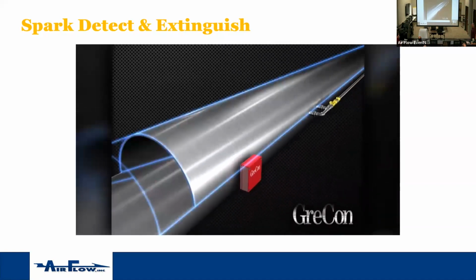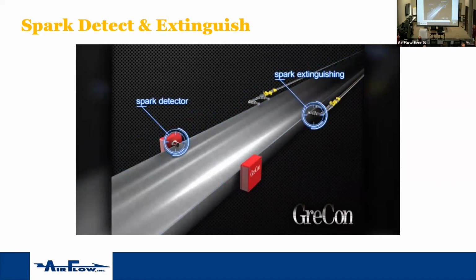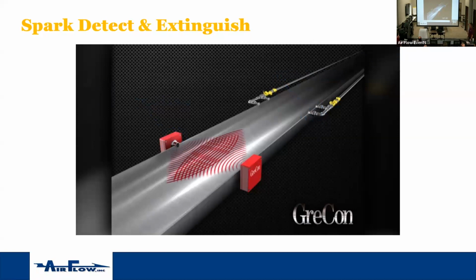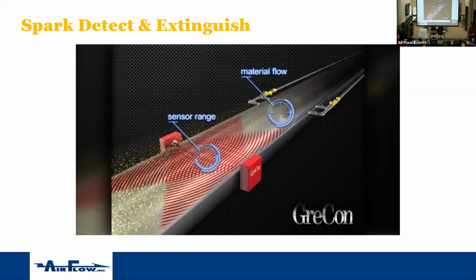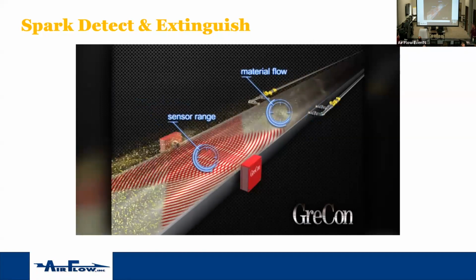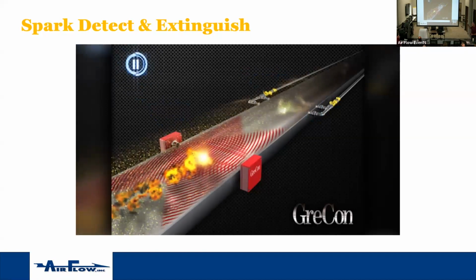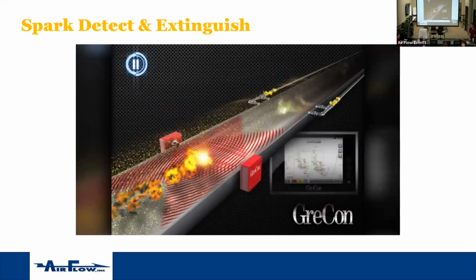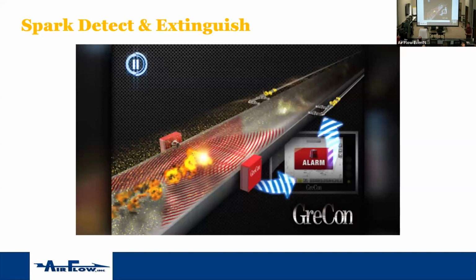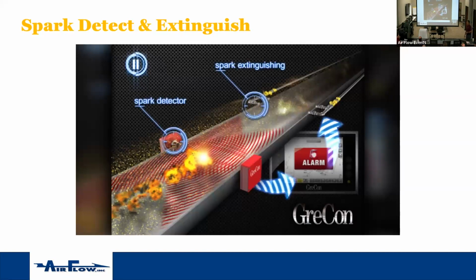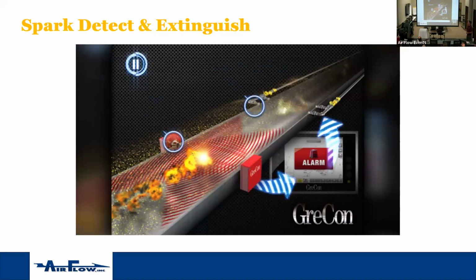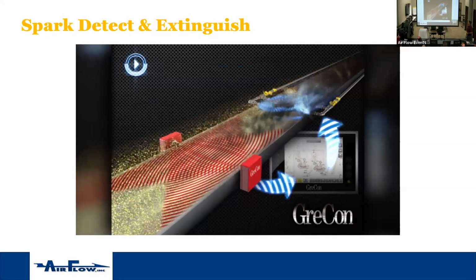One or two sensors get installed on either side of the duct. And all it is basically like a photo eye. It's just picking up a light source coming through your duct. So making sure your duct is sealed, the light is important. It'll sense a spark as it goes through the eye. It'll send a signal to the control panel. Control panel will recognize it's got a spark coming through, and it sends a signal to the valves. Open up. And the valves will open, throw its mist, extinguish it, and then go back off.